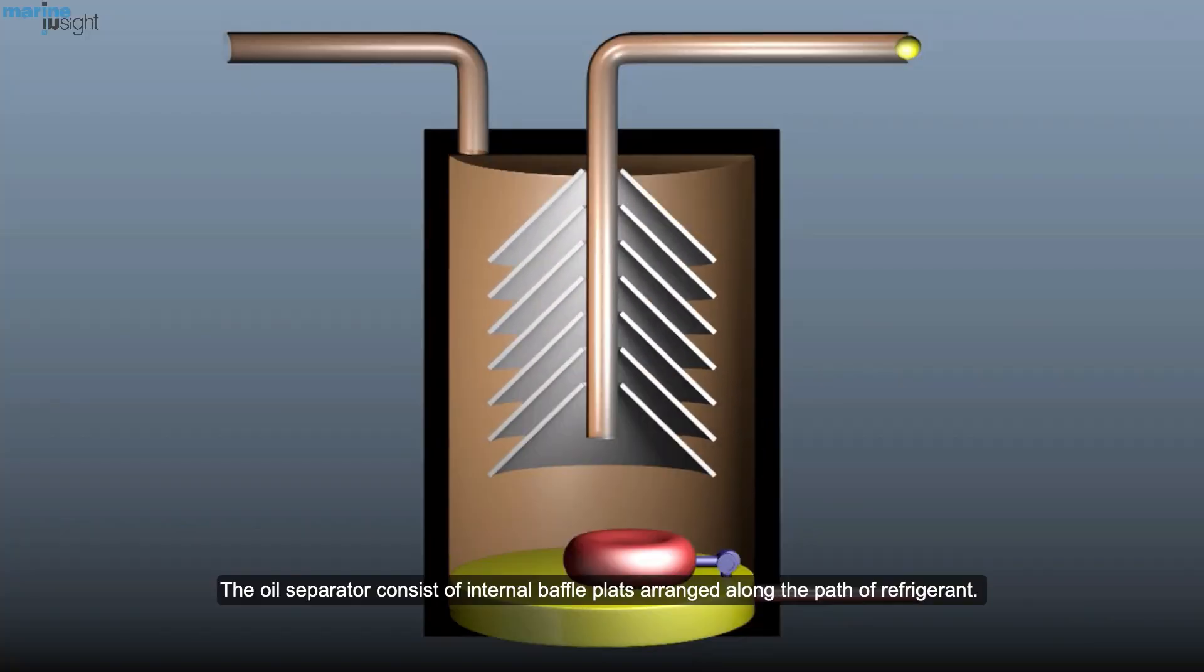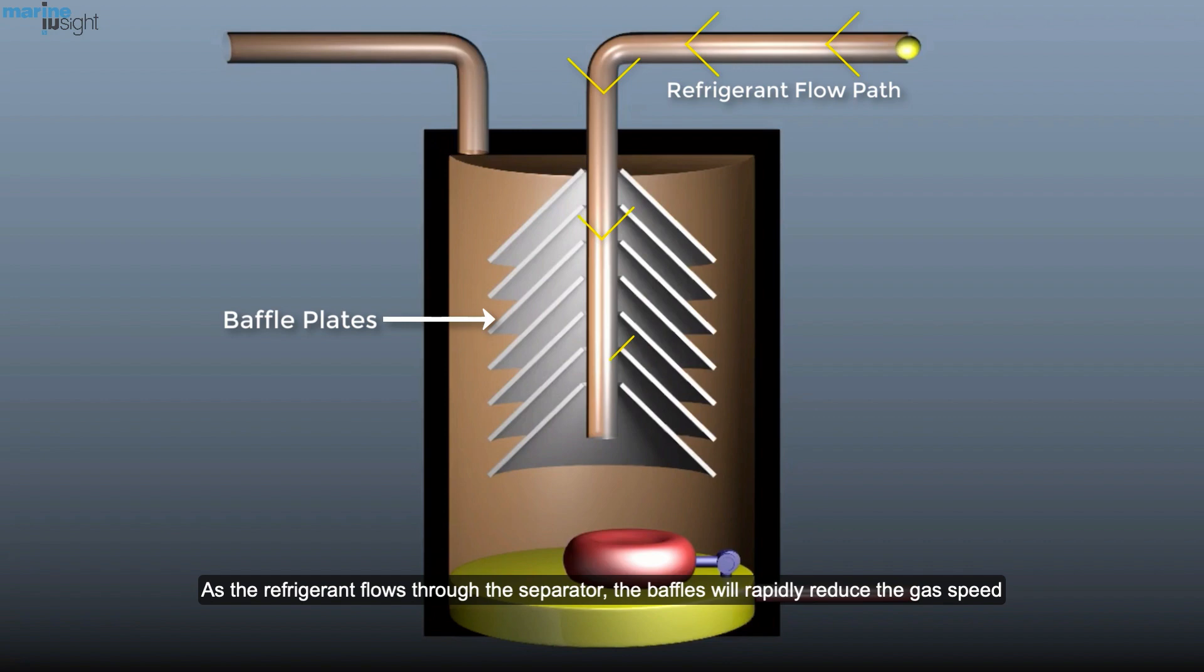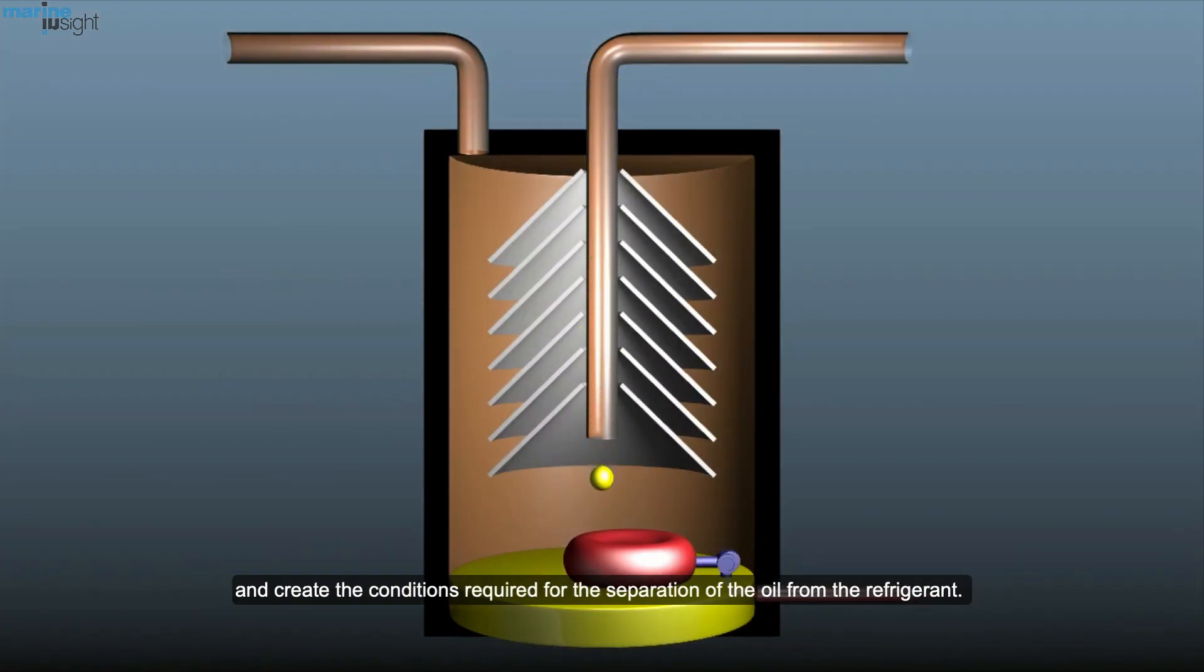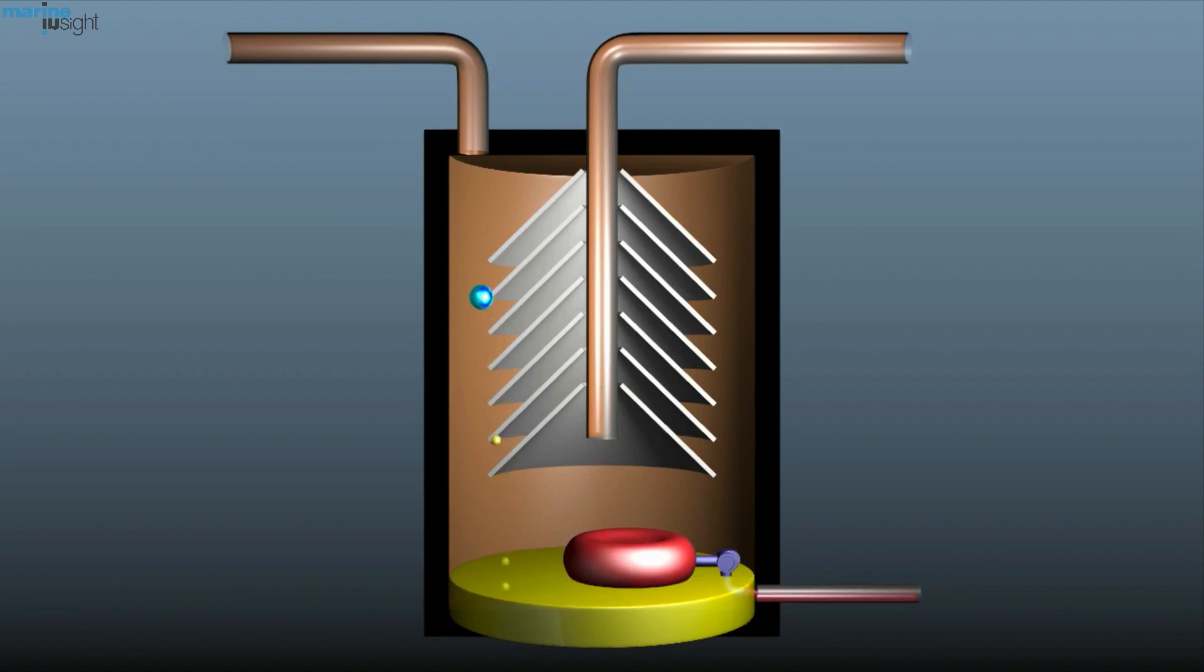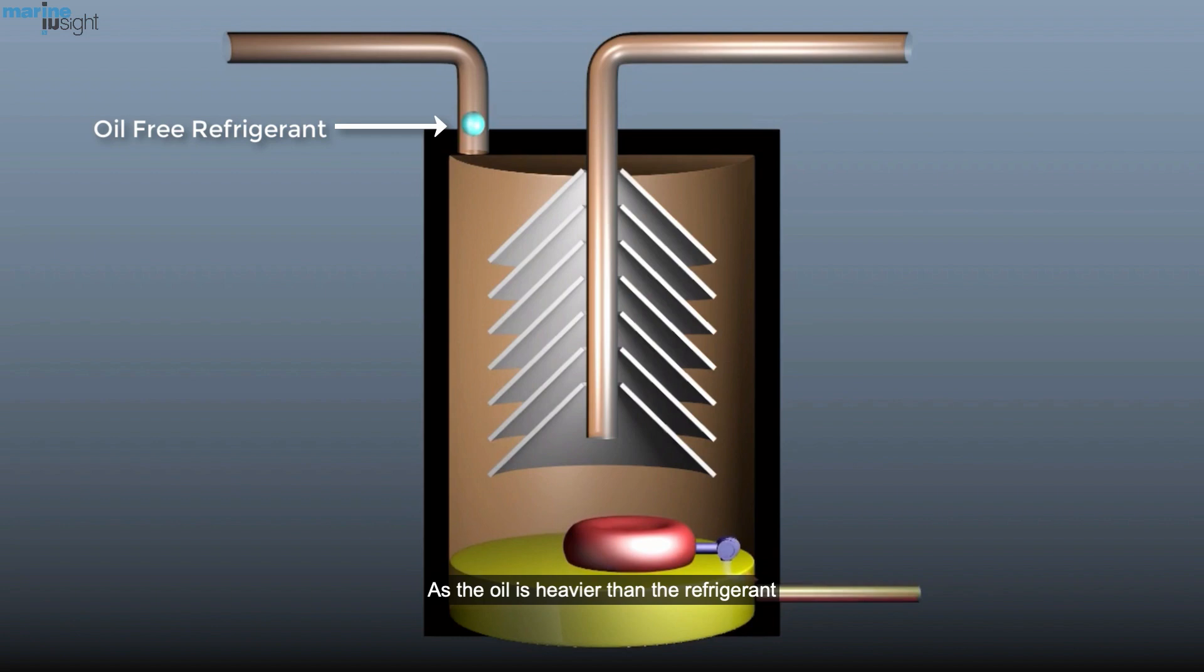The oil separator consists of internal baffle plates arranged along the path of refrigerant. As the refrigerant flows through the separator, the baffles will rapidly reduce the gas speed and create the conditions required for the separation of the oil from the refrigerant. As the oil is heavier than the refrigerant, it gets collected at the bottom of the separator.